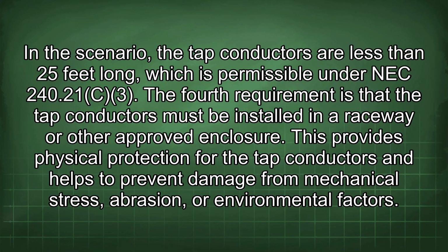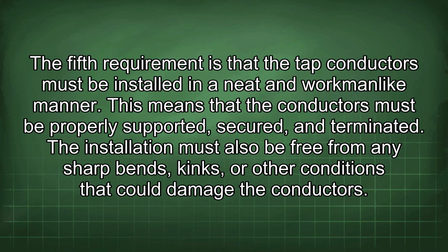This provides physical protection for the tap conductors and helps to prevent damage from mechanical stress, abrasion, or environmental factors. The fifth requirement is that the tap conductors must be installed in a neat and workmanlike manner. This means that the conductors must be properly supported, secured, and terminated. The installation must also be free from any sharp bends, kinks, or other conditions that could damage the conductors.